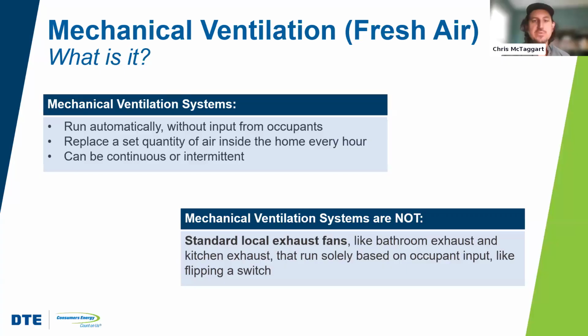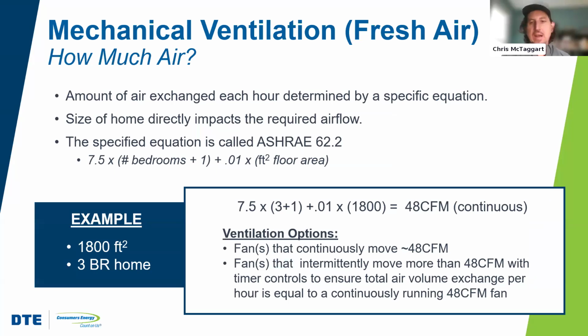And you can't just use a standard bath fan or standard fresh air intake and call that good enough. It has to be on some type of timer system or running continuously. How much ventilation air is allowed? You can use either the ASHRAE 2010 standard, 62.2 2010, or you can go to an even more significant version of ASHRAE that maybe has a slightly higher ventilation rate.